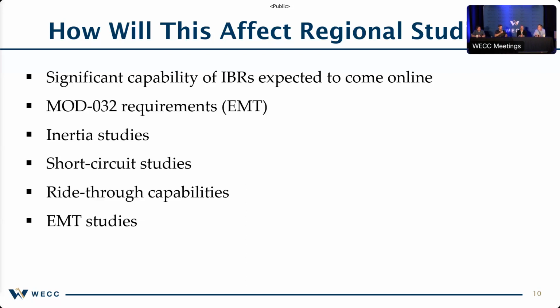And then short circuit studies. WECC currently is working on an assessment of how we see short circuit current changing with IBRs. 30,000 foot view: a traditional gas unit puts out about 6 per unit when you put a fault near it, so 600% of what it normally would be doing for its current output. That's how you identify a fault. Well, IBRs do about the same as when it was not faulted.